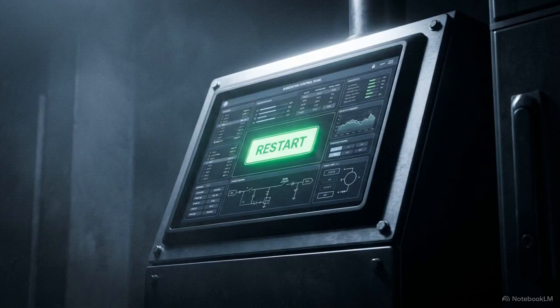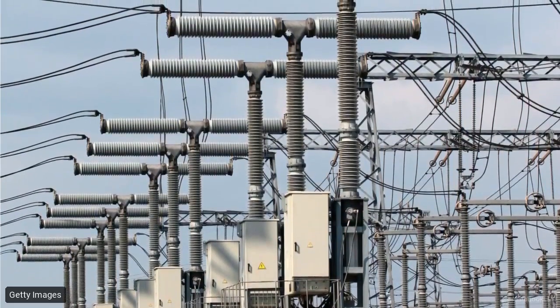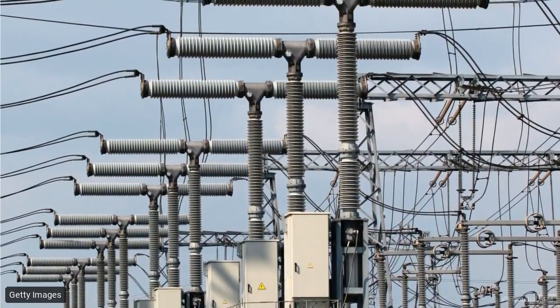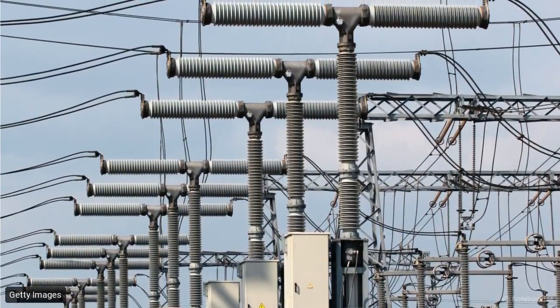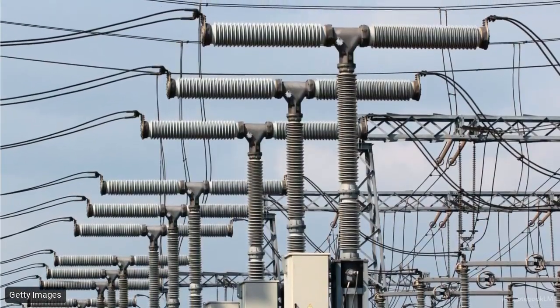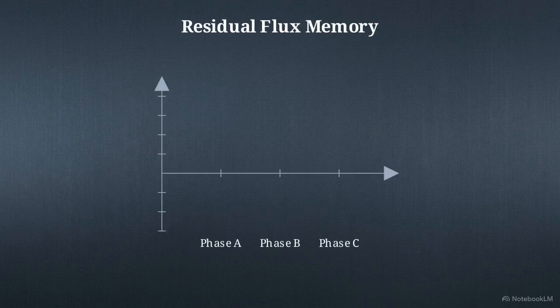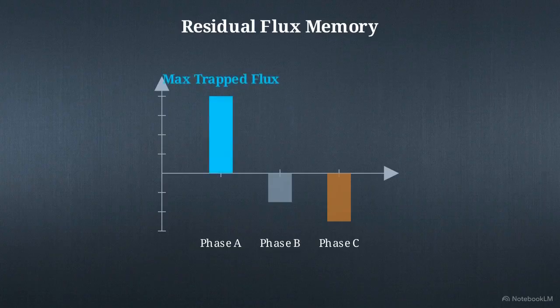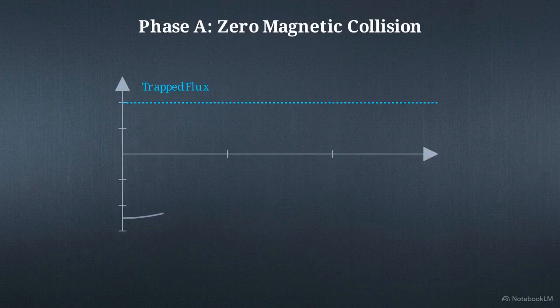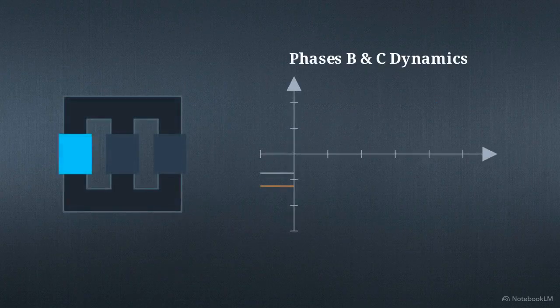When the re-energization command is finally given, the POW controller doesn't just throw a single switch. It initiates a highly coordinated sequence called independent pole operation, utilizing circuit breakers that can move each electrical phase completely independently. First, the controller checks its memory to identify which of the 3 electrical phases holds the highest trapped residual flux. Looking at this 3-phase chart, the controller fires that specific breaker at the exact millisecond the incoming source wave perfectly matches the trapped flux, resulting in zero magnetic collision.